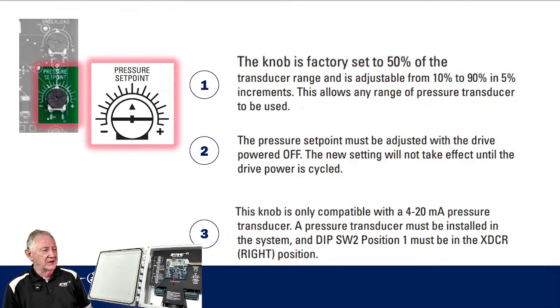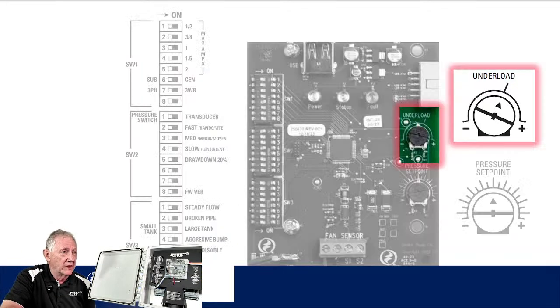The pressure set point must be adjusted when the drive is powered off, all right? So the drive needs to be off while we set that pressure set point. It says the new setting will not take effect until the drive power is cycled back up. And it says this knob is only compatible with a 4 to 20 milliamp pressure transducer. A pressure transducer must be installed in the system, and when it is, DIP switch bank number 2, position number 1, which is the transducer switch, must be in the right position, reading transducer, all right? But there's where you set your pressure. And again, when you set your pressure up there, it's going to be a percentage of the pressure range for that transducer. In the minds of a lot of contractors, this is a whole lot easier than setting a pressure set point with a pressure sensor switch.